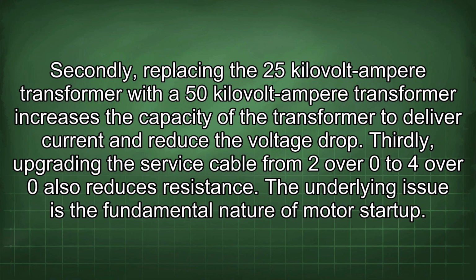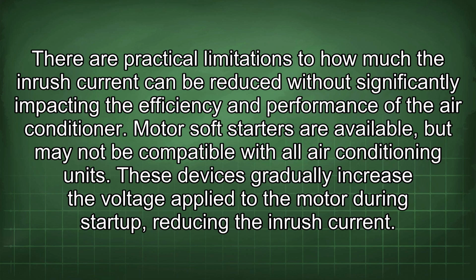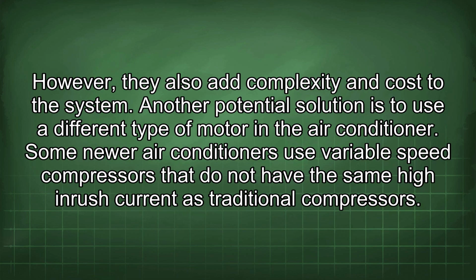The underlying issue is the fundamental nature of motor startup. There are practical limitations to how much the inrush current can be reduced without significantly impacting the efficiency and performance of the air conditioner. Motor soft starters are available, but may not be compatible with all air conditioning units. These devices gradually increase the voltage applied to the motor during startup, reducing the inrush current. However, they also add complexity and cost to the system.